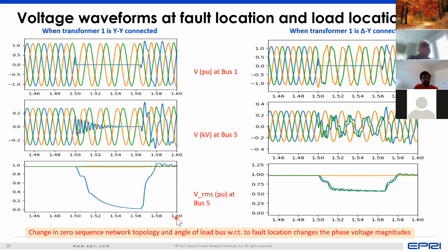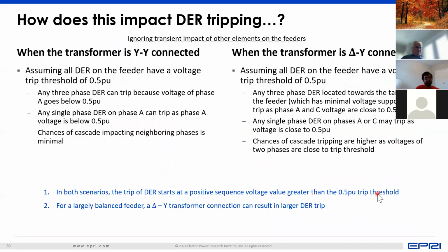DER tripping. But if the transformer is delta-star connected, you will see a voltage drop on two phases, but the voltage drop level will be higher, which means that DER on two phases now can be potentially impacted as opposed to when there was a star-star connection.